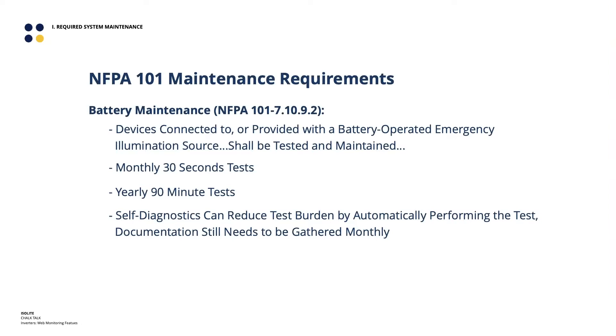The code requires monthly testing for 30 seconds and yearly testing for 90 minutes. The monthly test is really a nominal check — proving that everything is connected, that the charging and discharging circuitry works, that the battery is still connected, and that the lights come on. The yearly 90-minute test is more important because it determines that the battery capacity is still appropriate to meet Life Safety Code — that 90 minutes of runtime required.